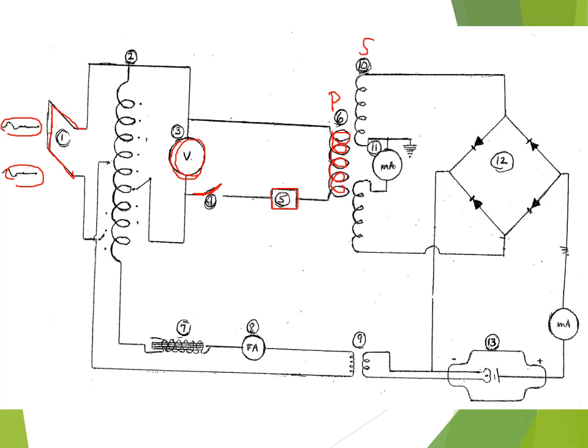And the primary side is in the low voltage or primary circuit. Now on the other hand, we have number seven, which is the mA selector. We have three types of mA selectors. This one happens to be a choke coil, but we also have two other types. There's also the rheostat, which is a resistor with the ability to change it. And then we also have the saturable reactor, which is the ability to have a DC, direct current, with a rheostat.